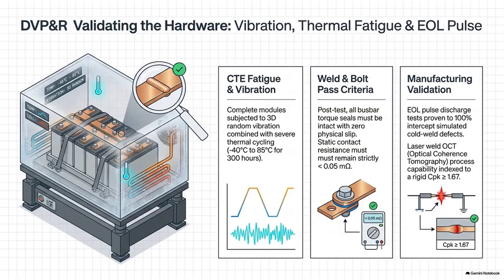And the passing criteria they are looking for is aggressively strict. The source document says the contact resistance must be less than 0.05 milliohms, 50 millionths of an ohm. They're basically zero. That is essentially proving that the joint is electrically indistinguishable from a solid, uninterrupted block of copper. Exactly. If a laser weld suffered from that plasma keyhole collapse we talked about and formed a microscopic void, the 4-wire Kelvin measurement will detect that the resistance is, say, 0.08 milliohms. And it fails. And the pack will be flagged and rejected before it ever leaves the facility.